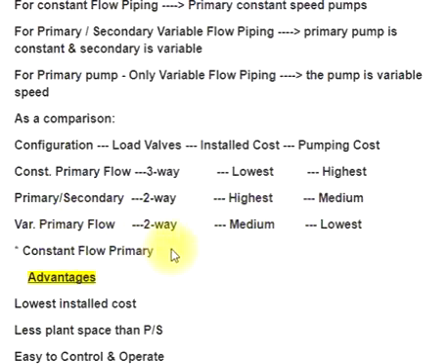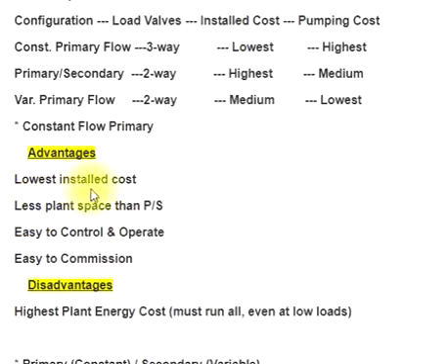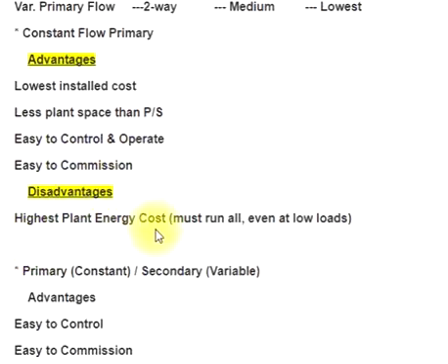Constant flow primary advantages: lowest installed cost, less plant space than primary-secondary, easy to control and operate, easy to commission. Disadvantages: highest plant energy cost — must run all chillers even at low loads.